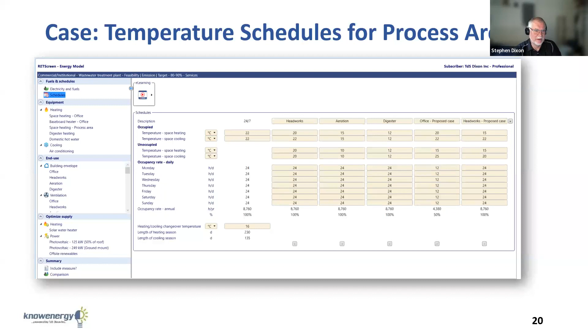It's an auxiliary system in a sense, the heating of the building, but it's definitely an energy consumer. Then we look at maximizing efficiency. This can come down to how we keep things clean: heat exchangers, pipes, ducts, coils, filters, and lubrication, all those things. Combustion equipment having it regularly tuned up, optimizing how systems like pumps, fans and blowers are operated to make sure we're operating at the most efficient point, and we're also meeting the needs of the process properly.